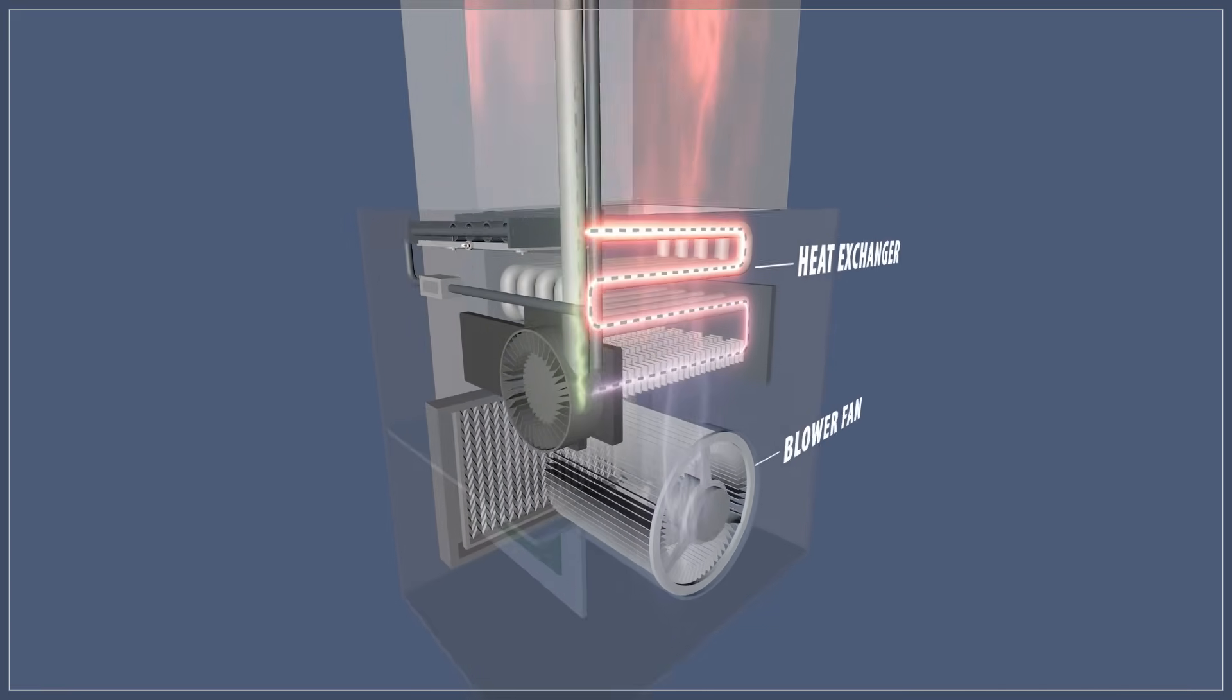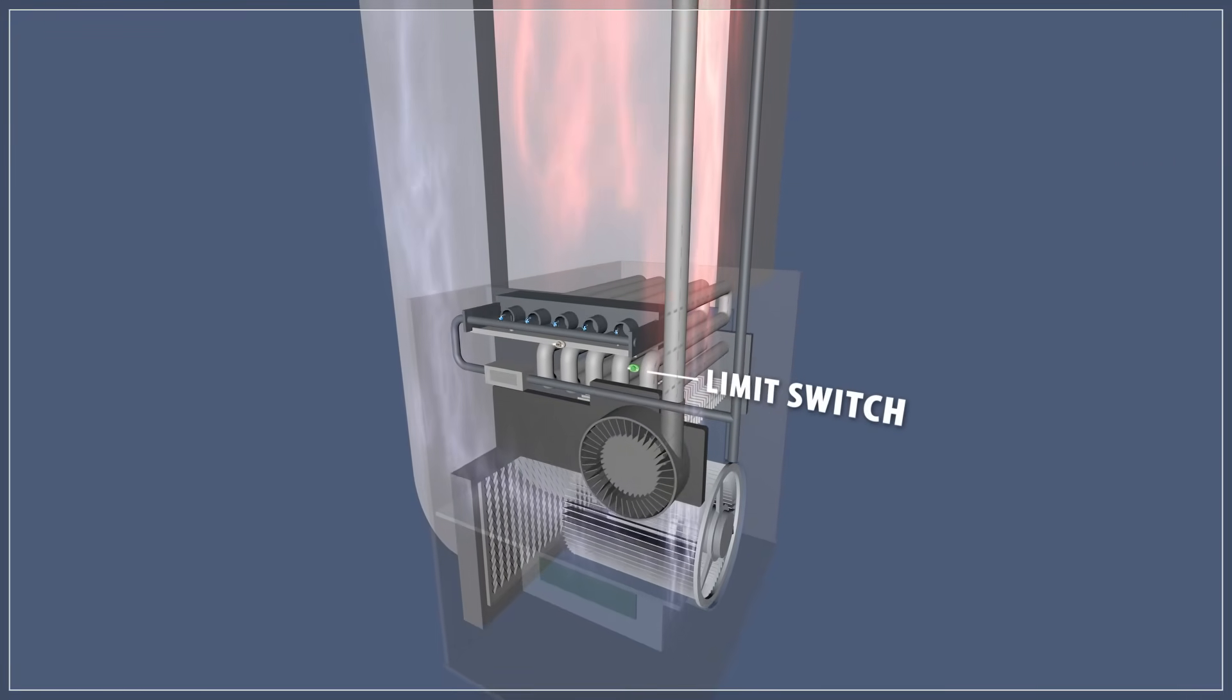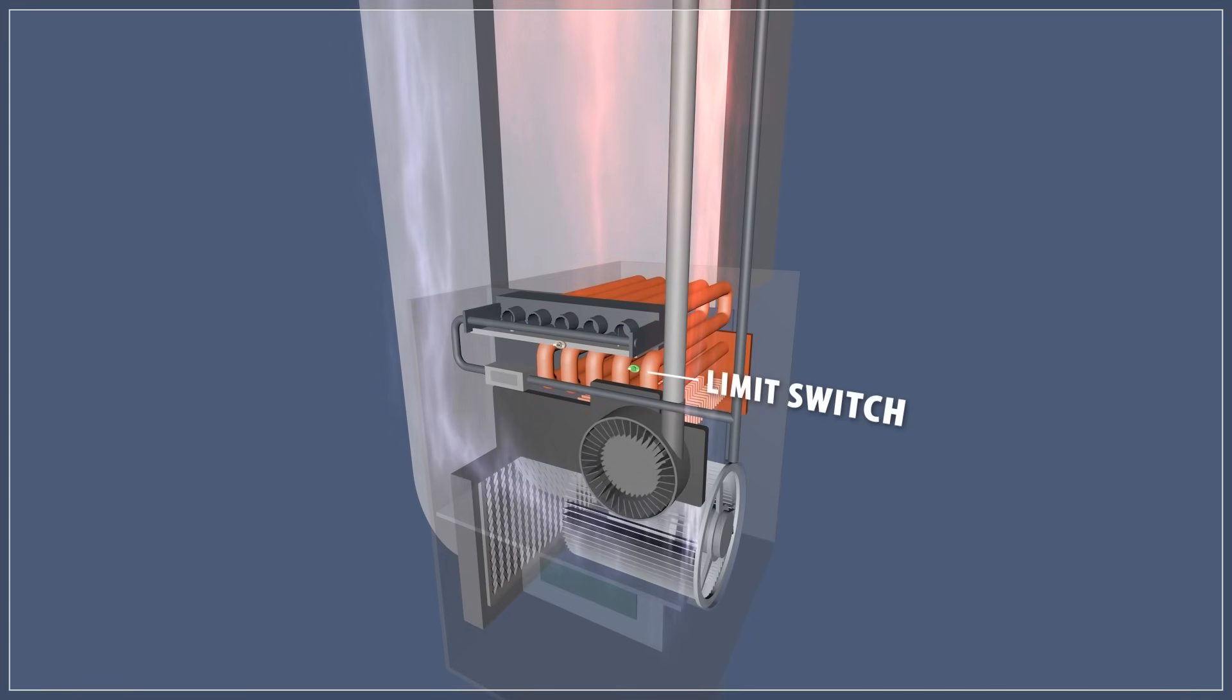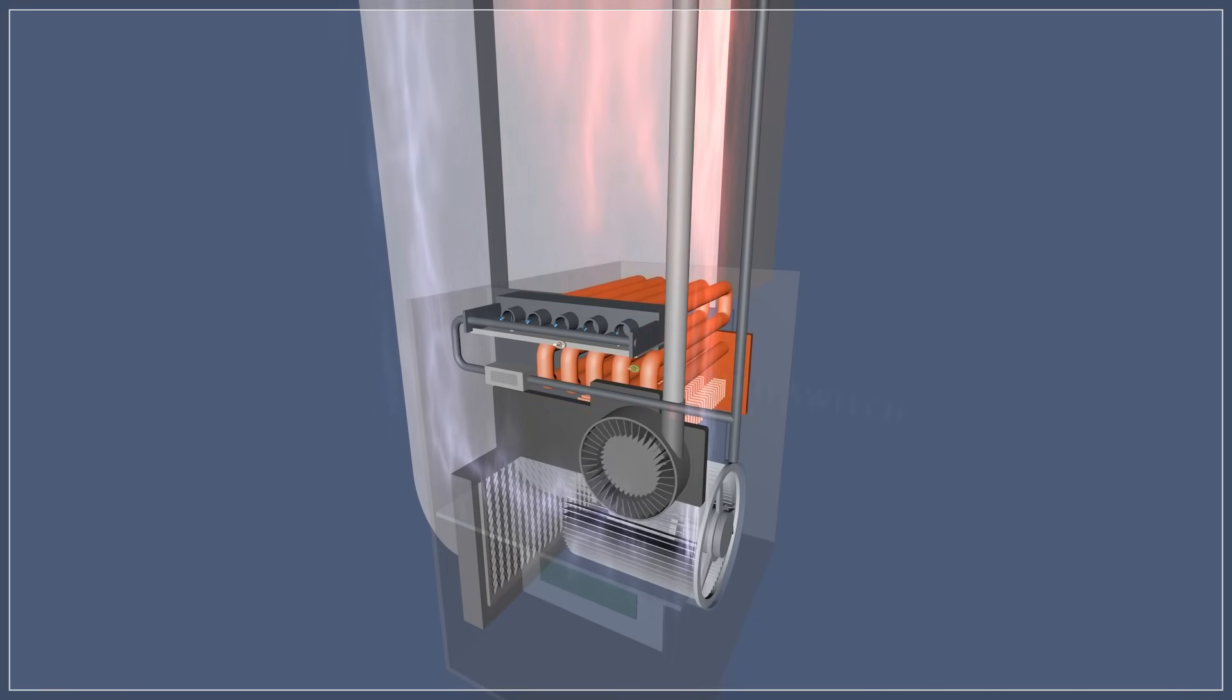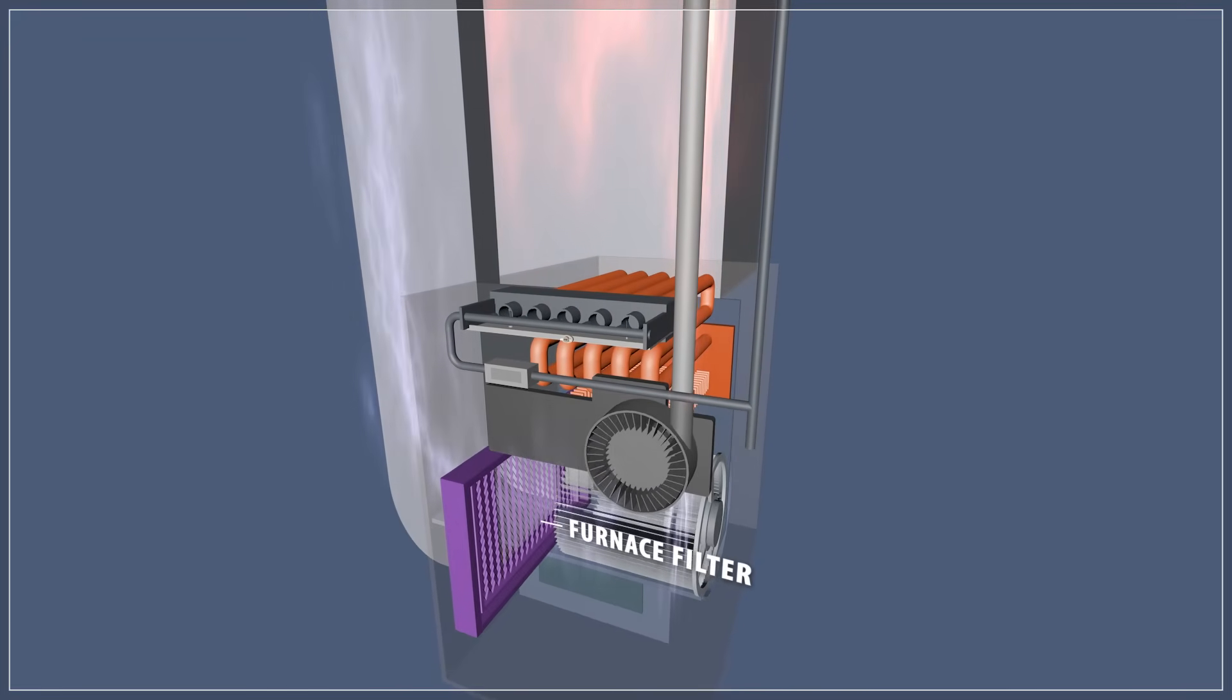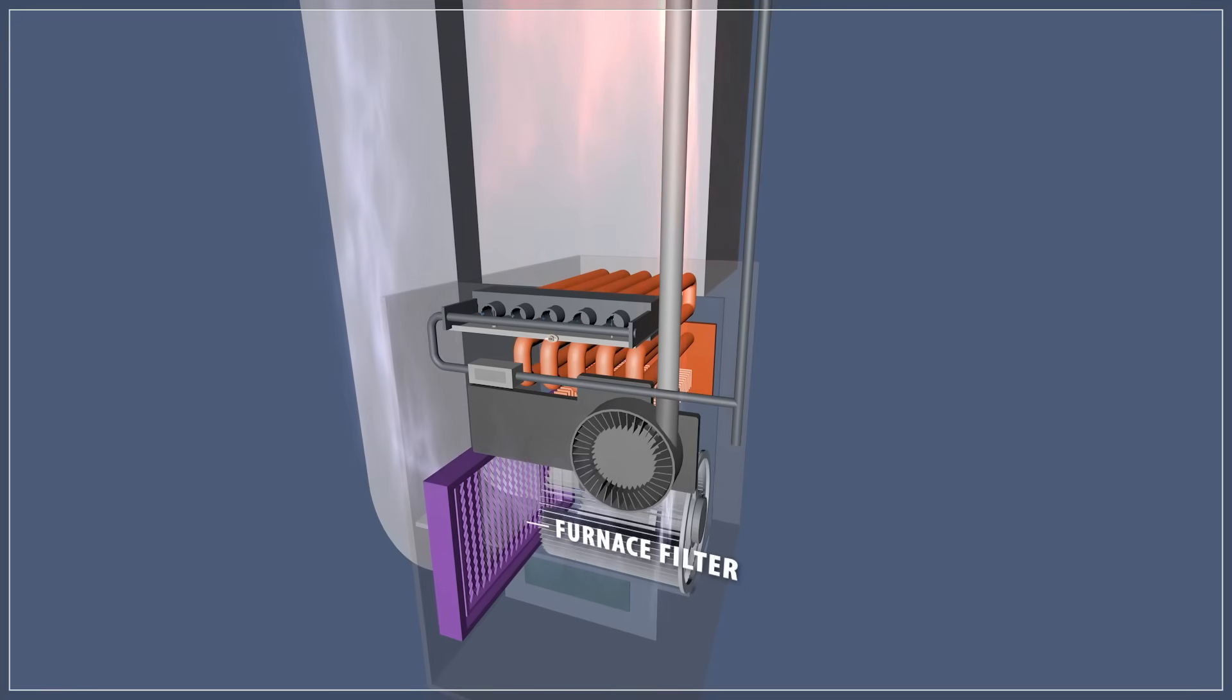The limit switch monitors the temperature of the air passing over the heat exchanger and will shut off the furnace if the system overheats. Any restriction of the air flow might cause the heat exchanger to overheat. That's why it's essential to replace the furnace filter every 3 to 6 months.